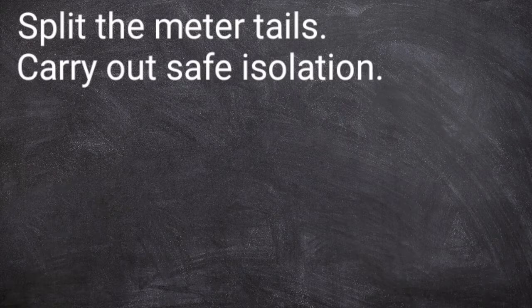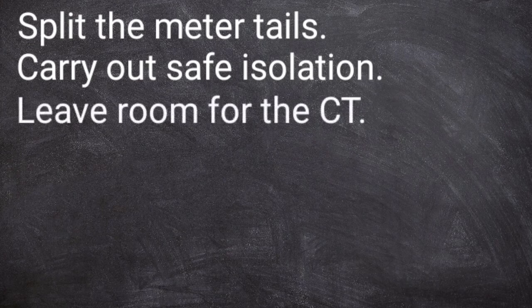Absolutely, and of course, if we were to move away from the energy meter where the isolating switch is, we'd want to make sure that remained locked off so that nobody could turn that back on and become injured in any way. All of our equipment must conform with what, Gary? Our testing equipment should conform to GS38 and all the requirements for that, and we should also, as shown in the video, prove our test equipment before and after using it. Excellent, yeah, following very carefully all the safe isolation recommendations that have been published from various sources. As this work's progressing, it's very important to make sure that we leave room for our CT to be installed onto the cable.